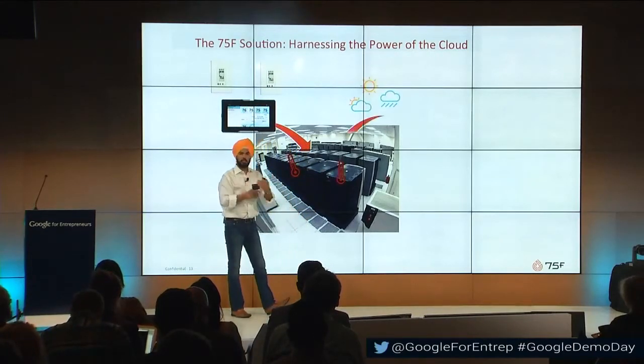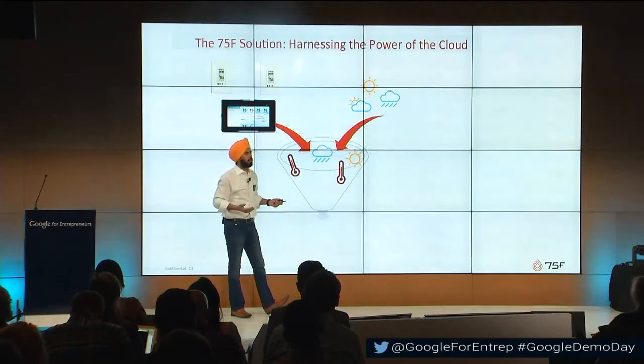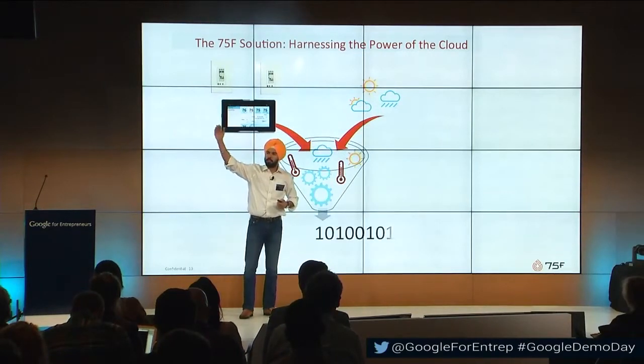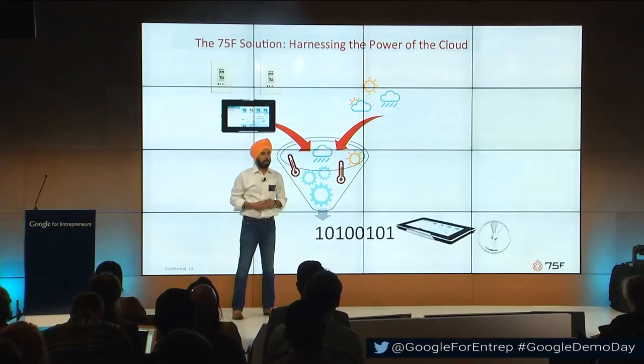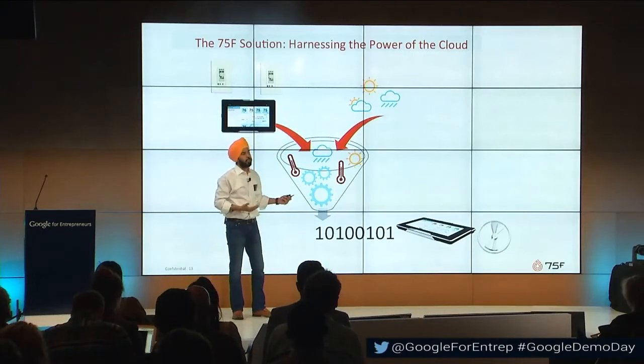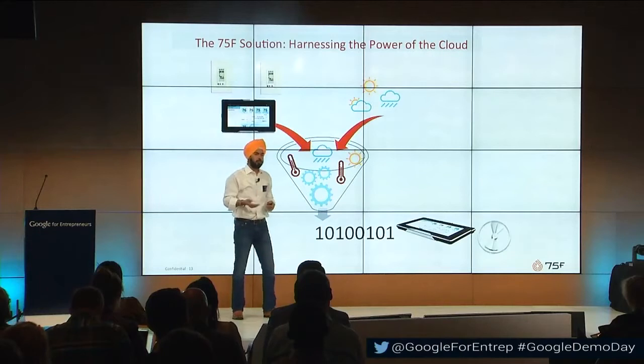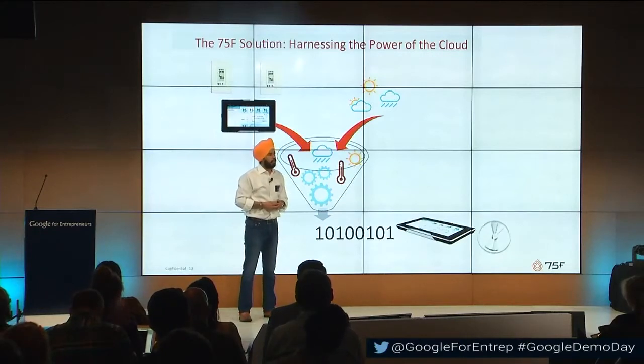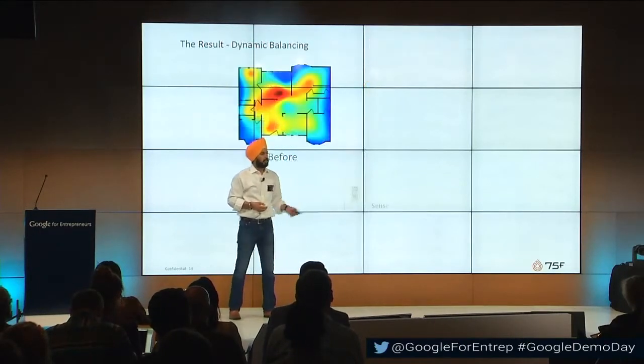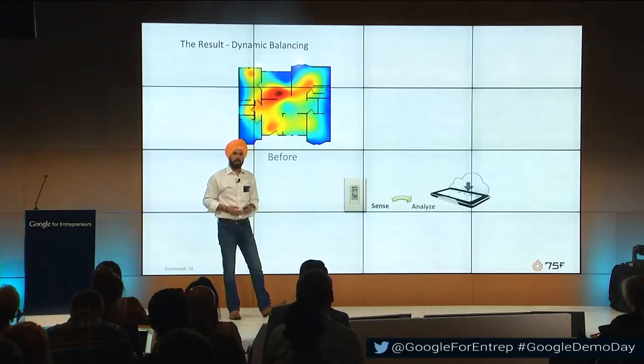Every night we crunch this historical data and we create a thermal model of the building. We then look at the forecast weather and we predict how the building is going to be behaving, and we figure out an optimal control strategy, which is then sent back into the CCU, which proactively controls the HVAC equipment during the day. The system constantly learns and adapts to changes in the weather and heat loads.